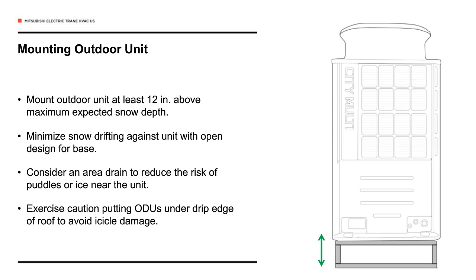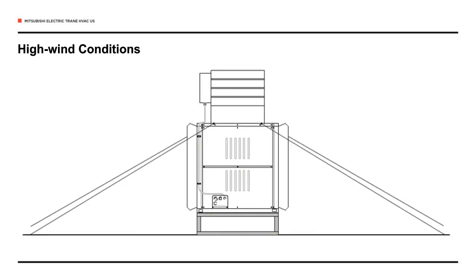Then there are high wind conditions. If you have a unit or units that are up on a roof and they're exposed and they just catch the wind, if you have low ambient kits like is shown there or snow hoods, these things get pretty tall and have a fair amount of surface area, so you want to make sure that you support them properly with guy wires. If they're outside next to the building and protected by the building itself or fencing, you generally don't need this, but this is where you have exposed locations.